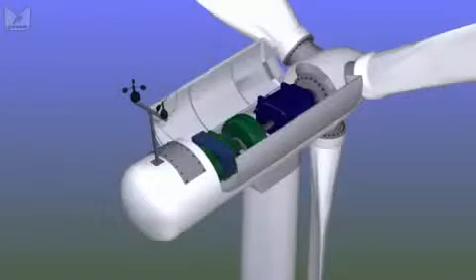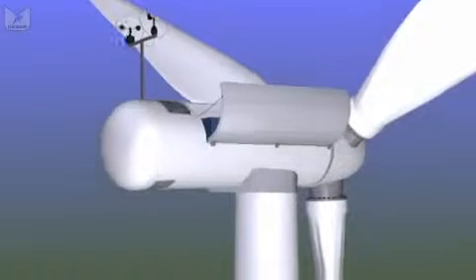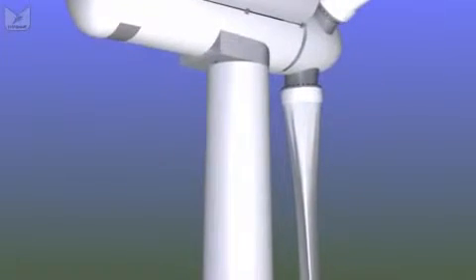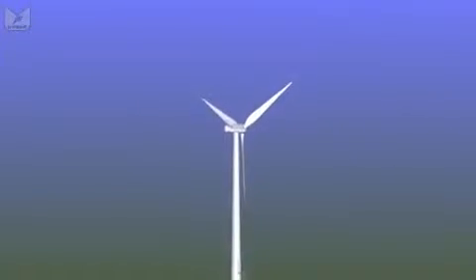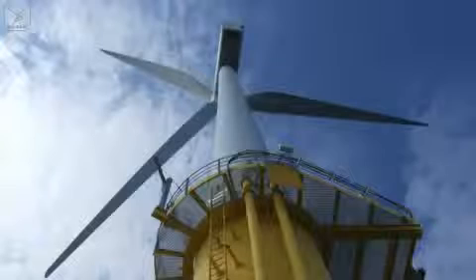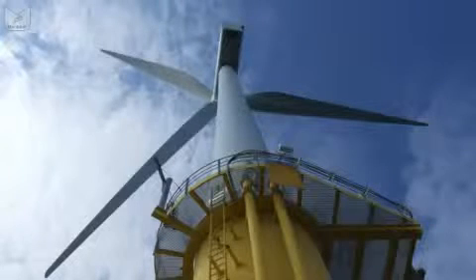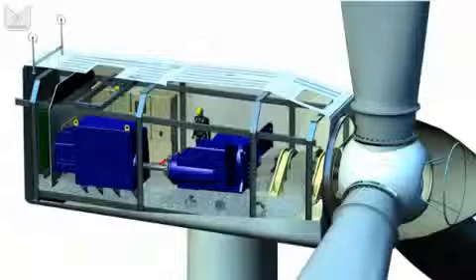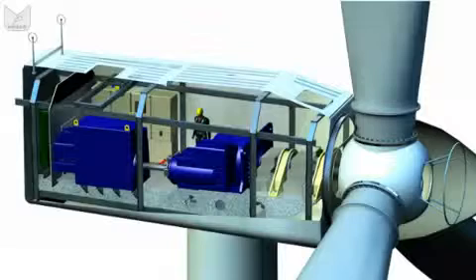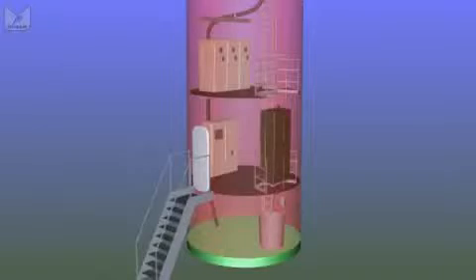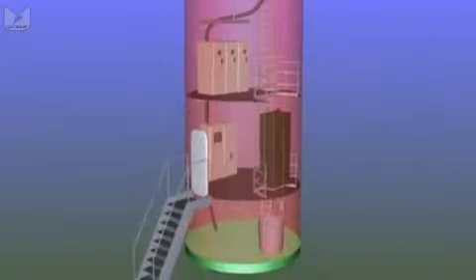Now the layout of a larger turbine is broadly similar, but some of the components are in different places, so let's start by looking at the tower section of a typical 2-megawatt turbine. Where we place the high-voltage transformers in multi-megawatt turbines is a lot more variable. Quite frankly, we have a lot more room, so we can decide. They can be in the nacelle, they can be at the base of the tower, they can be on platform 1 in the basement, they can be outside in a hut. In this example, the transformers at the top, so when we go into our door, the one thing we'll not find is a transformer.